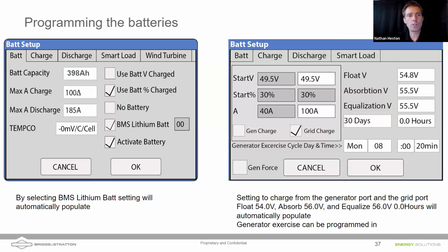Enable that, then set your maximum charge and discharge limits. Those can be set for a 3-stack up to 195 amps on the charging side. On the discharging side, the max of the Sol-Ark you can set at 273 for a single stack of our batteries. The Sol-Ark will probably only use about 250 amps, which is around 12K for a 50-volt battery.